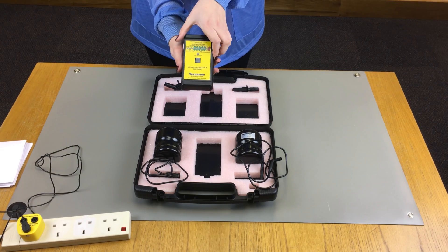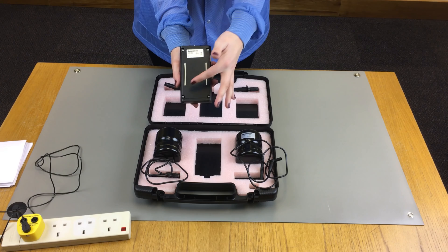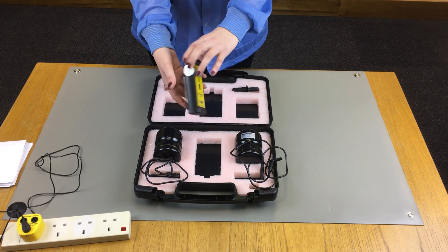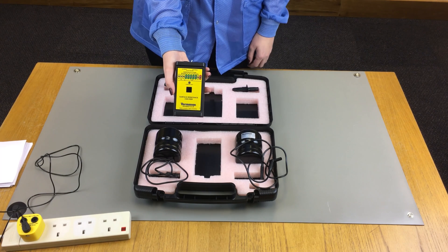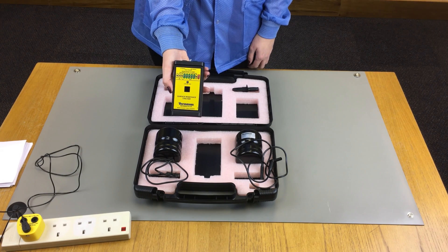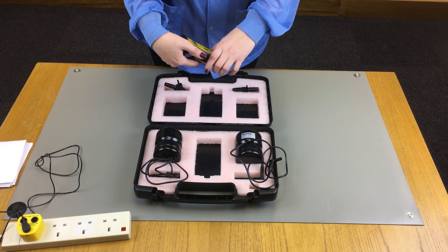The Vermason Surface Resistance Checker is a portable battery powered checker fitted with built-in parallel electrodes. These electrodes allow for a quick verification of point to point surface resistance. The unit, together with the leads and electrodes, can also carry out a point to point surface resistance test and a resistance to ground test.